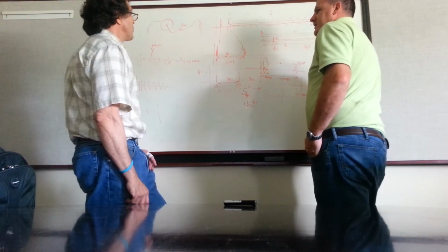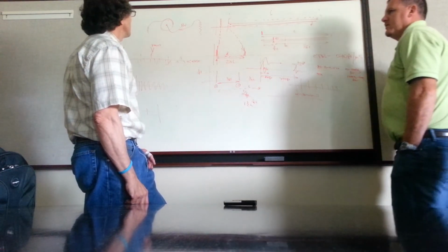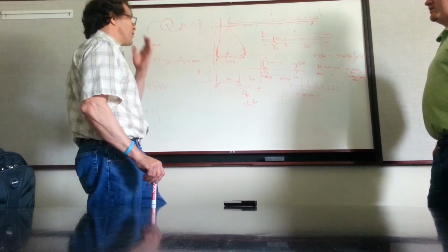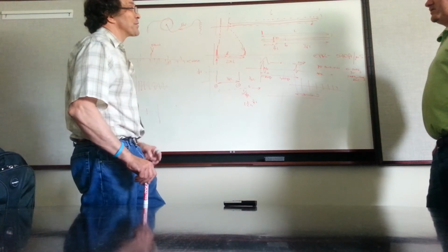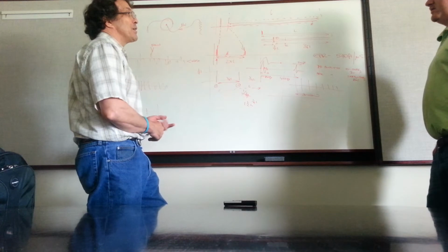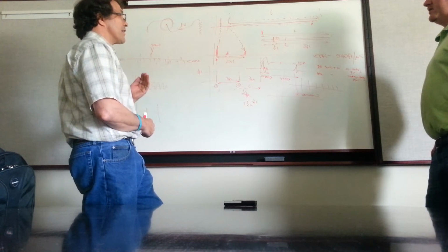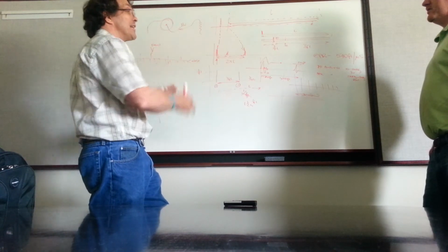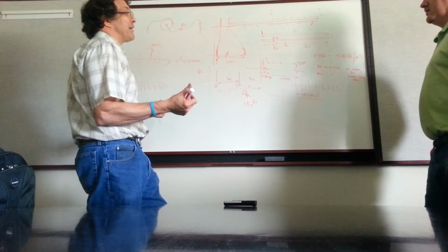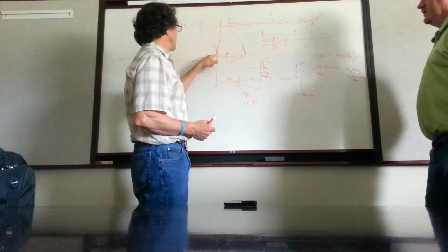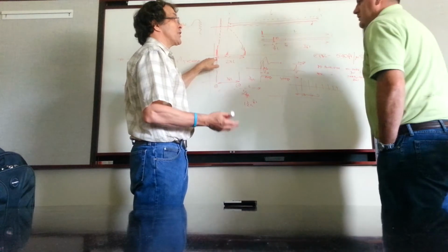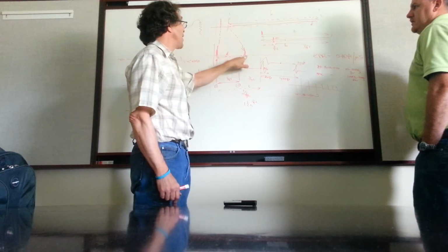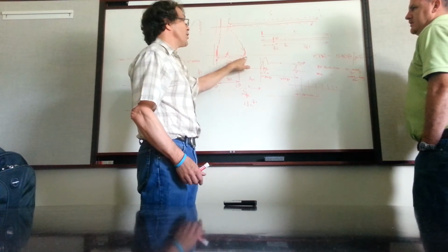Well, what I think would be the easiest way to deal with it is to ignore the terminology of top and bottom. That's only any use to you when you look at the text they use. To us, top and bottom has no meaning. To us, it's either start and finish, or to the system when you're doing location, it's powered end and non-powered end. So this pulse always belongs to the powered end. Doesn't matter if it's the start or finish of the reel, top or bottom. It belongs to the powered end. The tail pulse, we call it the tail, but it's still the non-powered end.